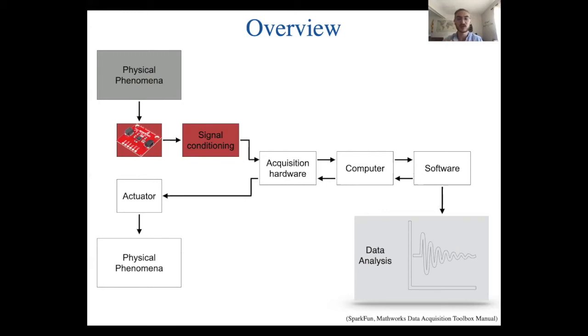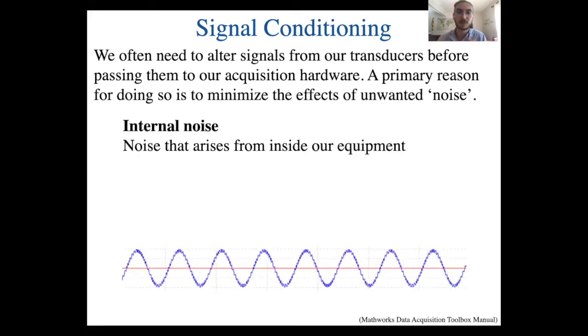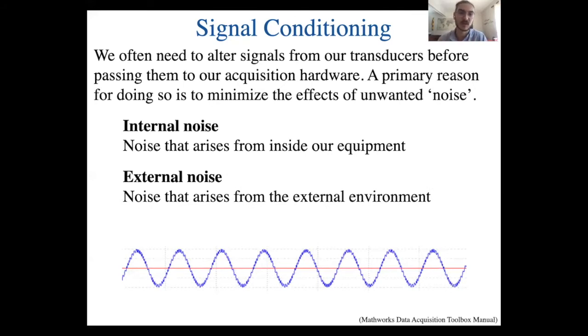Now we're at the point where we have used a transducer — the sensor — to go from some physical phenomenon to an electrical signal, which in many cases is a voltage. The next step is what we call signal conditioning, where we might decide to alter our signal before sending it to our acquisition hardware. More times than not, the reason for signal conditioning is to remove noise. Noise can come from different sources — internal noise from inside our equipment, or more commonly noise from external sources, such as 60 Hz from incandescent lights or 120 Hz from fluorescent lights.